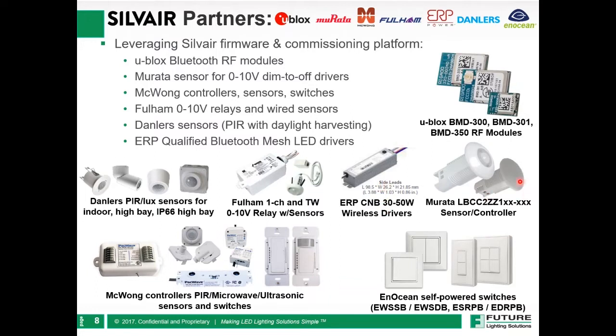Silvair has created the firmware and commissioning platform to enable multiple vendors of products, controllers, sensors, wireless LED drivers, switches, and all related technology, whether indoor or outdoor, 0 to 10 volt or DALI. The Bluetooth mesh standard was defined to be interoperable, so you're not required to use Silvair. It's just the most proven platform, but you're not exclusively tied to it, which brings a lot of freedom when you have a project and want a choice of different hardware platforms that will work together.